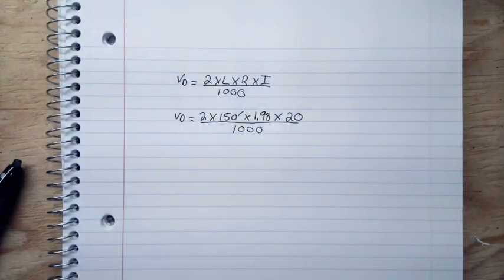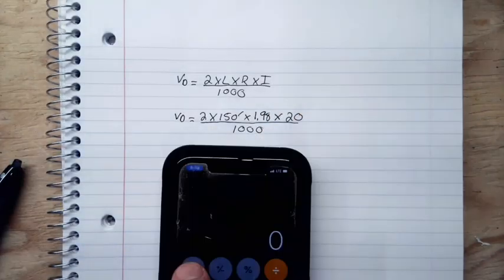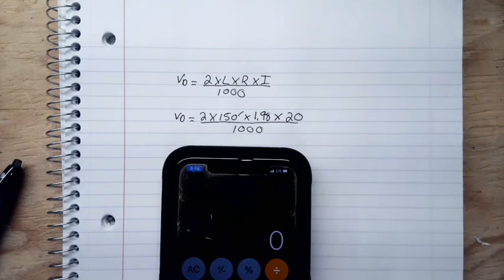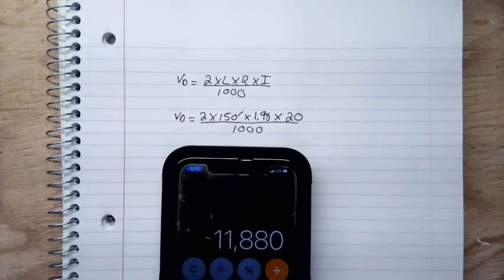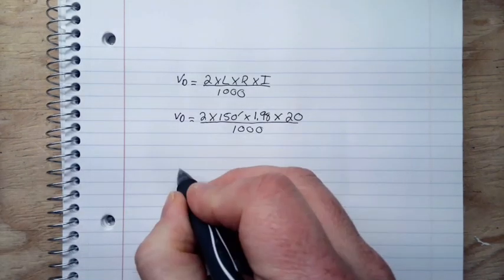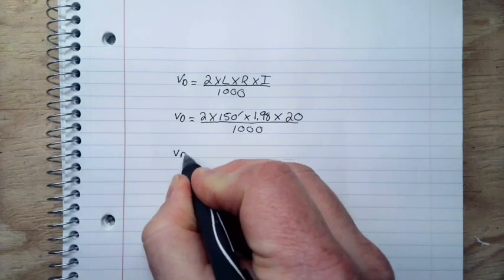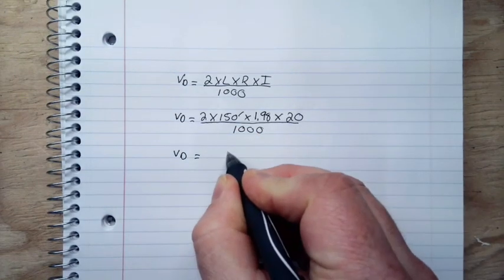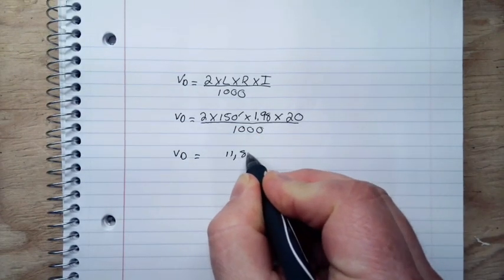Now it's as simple as doing the math. Bring up my calculator here. I'm going to do 2 times 150 times 1.98 times 20, which will equal 11,880. So what I'm going to do now is continue to write this below. VD, all of these together came out to 11,880.